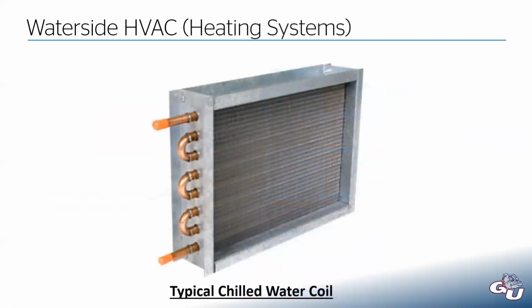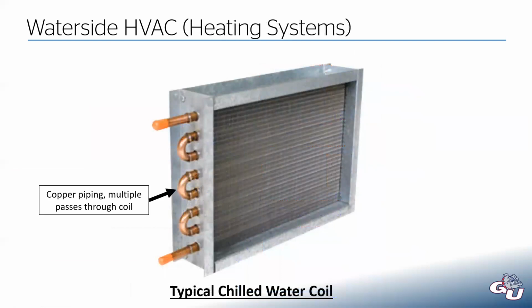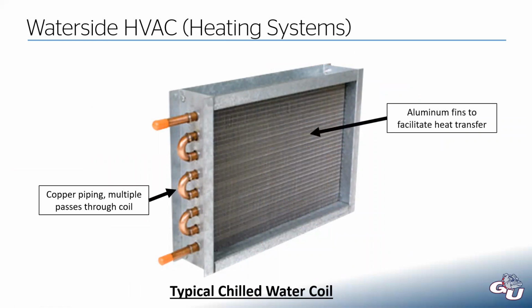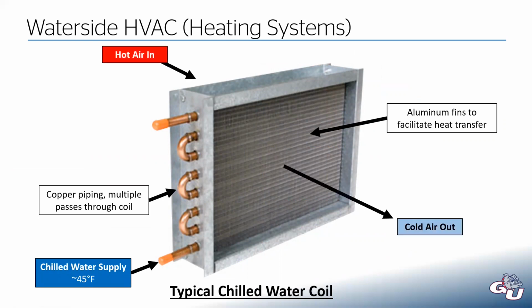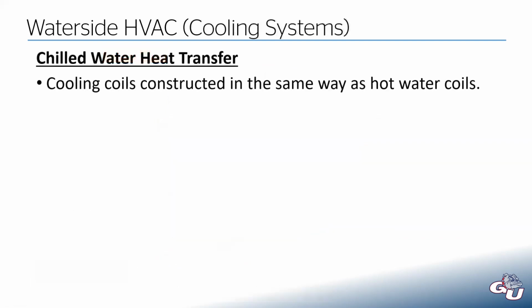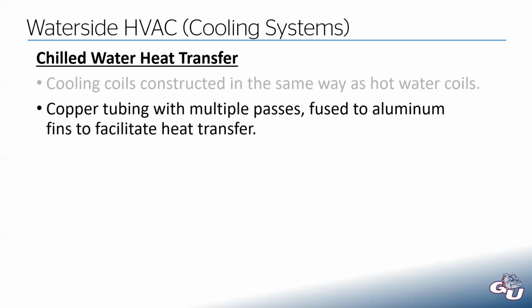On the coil side, just like hot water, it's very similar. So we have our copper piping, we have aluminum fins to help make that heat transfer happen. We're going to pump in our cold chilled water supply at around 45 degrees. Hot air goes in, cold air comes out, and then our water comes out about 10 degrees warmer. So this coil is constructed the same exact way as it is for a heating coil. There's really no difference at all. The only difference you might have is to get the heat transfer we need, we might need more passes through the coil or more aluminum fins per inch of coil or something like that. So we have our copper tubing fused to aluminum fins. It's all the same.